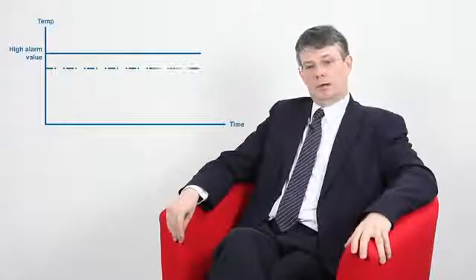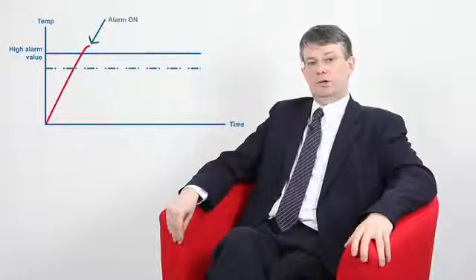Another useful feature found on some of our instruments is the adjustable alarm delay timer. With this, when the alarm value is reached, instead of the alarm activating immediately, a timer is started. Only if the alarm condition has been present for the entire duration of the alarm time set does the alarm actually activate. This can be used to prevent nuisance alarms caused by momentary disturbances in the process. Another example of its use is to prevent product from being drawn off from a process unless it has been at a certain temperature for a certain amount of time — for instance, because the process has a temperature-dependent chemical reaction that can only take place after the correct temperature has been reached.